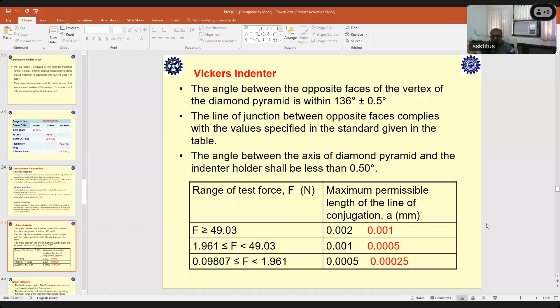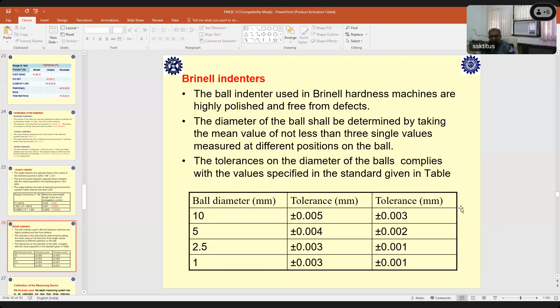Similarly, the ball indenters used in a Brinell hardness machine are highly polished and free from defects. These are all important factors, because we cannot use just any type of ball. It also has to satisfy all the requirements: how polished it should be, how defect free, and what the curvature should be. All these things are mentioned in this standard. I have given you the values here in numbers. If it is a 10 mm diameter ball, then the tolerance should be plus minus 0.005 mm. That is for the testing machine indenters, and this is for the calibration machine indenters. It has to satisfy all these requirements.